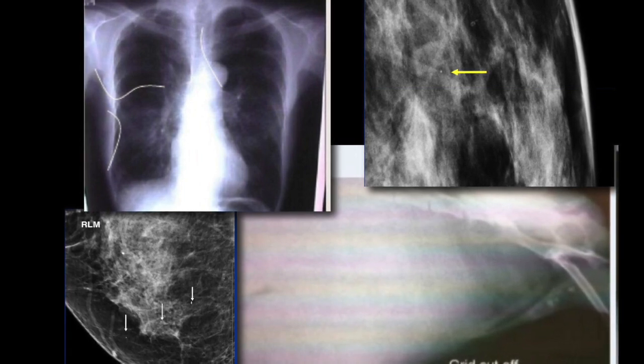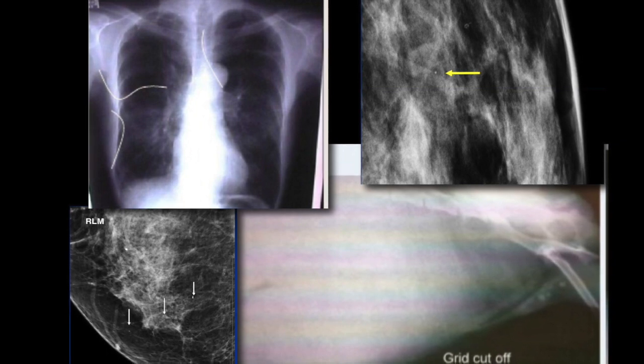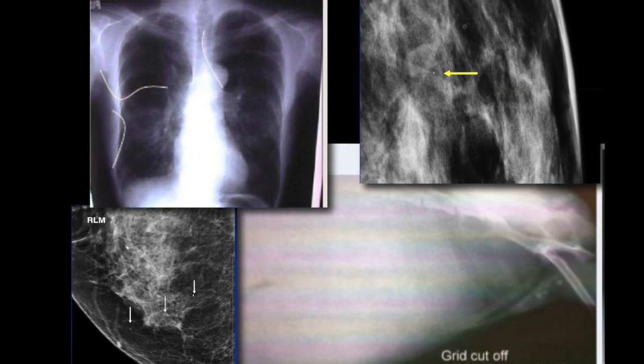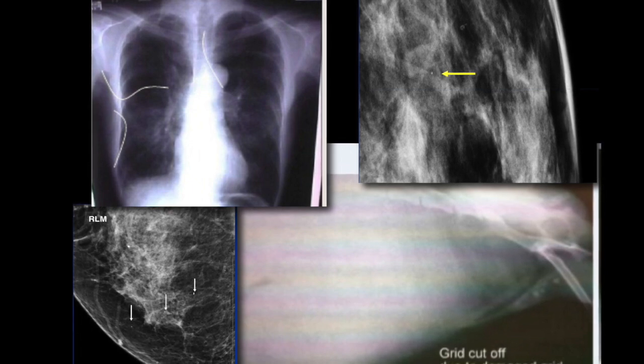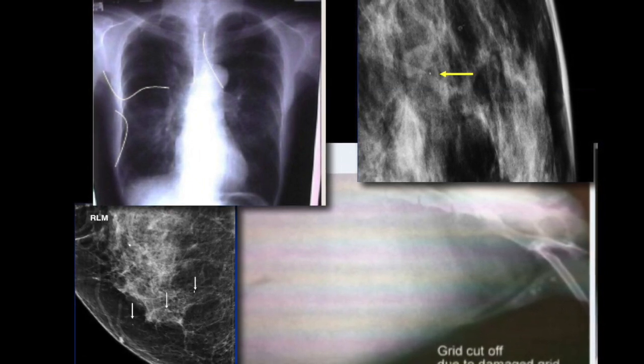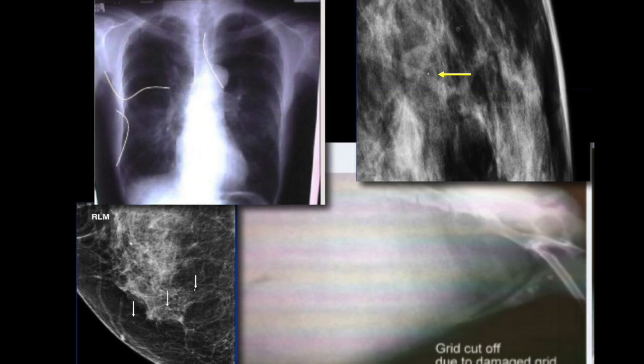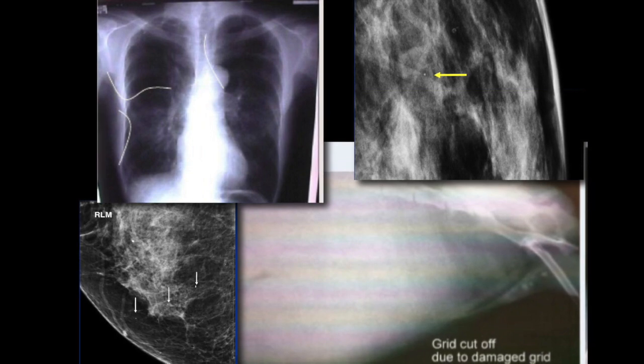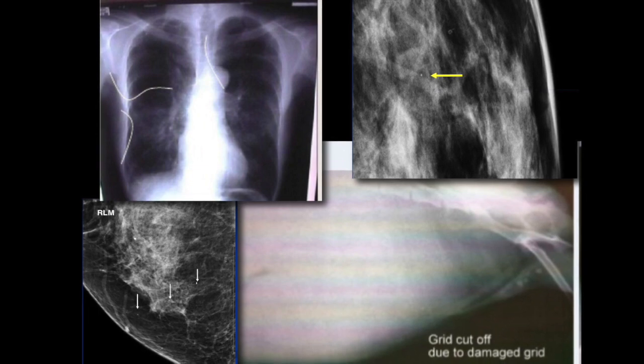IPs, PSPs, and cassettes should be kept clean, dry, and care should be taken to prevent physical damage that could affect their ability to be read through the scanner or cause artifacts in the image due to dust and scratches. They should also be routinely checked for artifacts that, if not realized, can present as radiologic findings on a patient's exam. Cassettes are constructed to protect the sensitive PSP plates contained within them. The cassettes should be held on their edges and stored vertically to prevent warping. Extreme temperatures and contact with fluids should also be avoided. It is important to keep in mind that a dirty cassette can itself become a contaminant to patients and staff.